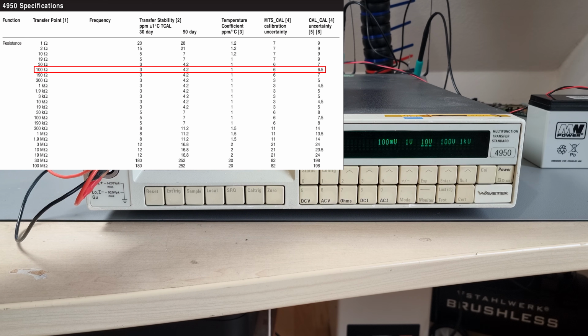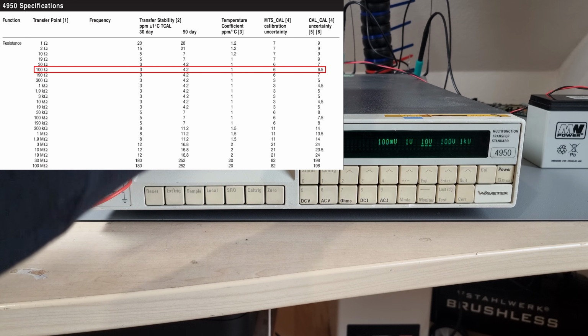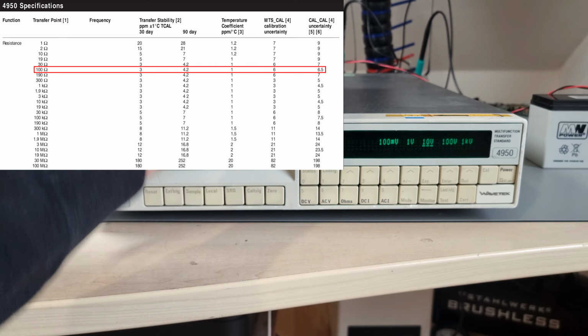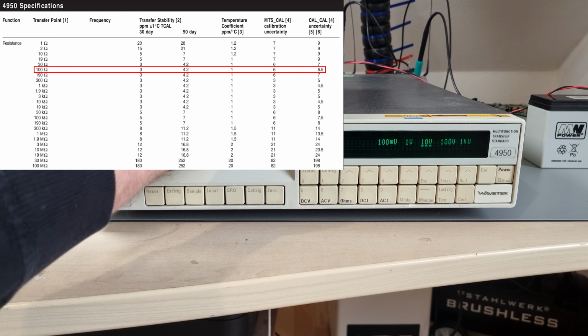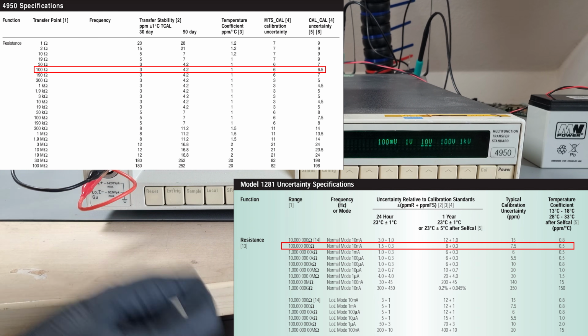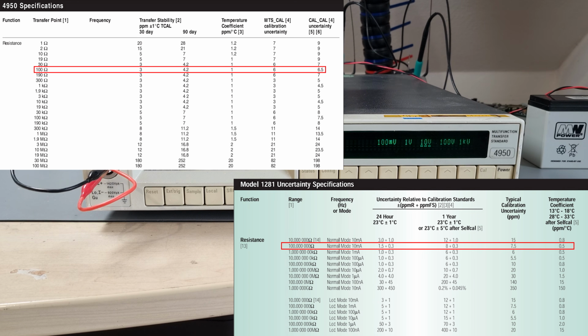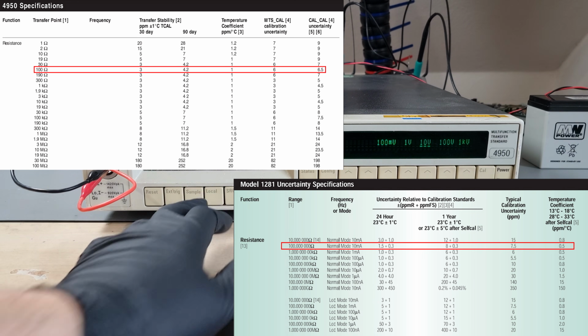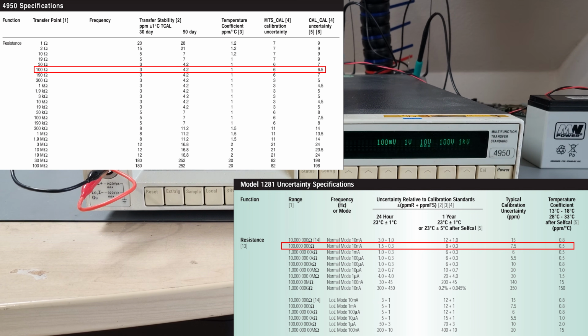Let's say when comparing a 100 ohm standard to another, the 4950 gives you a 30-day 3 ppm uncertainty and a 90-day 4.2 ppm uncertainty, whereas with a multimeter, a day after calibration, you'd instantly fall into the 1-year 8 ppm window. Arguably, the multimeter is not going to sit there 23 hours and 59 minutes after its calibration, impatiently looking at its wristwatch, waiting to lose accuracy all of a sudden. If lucky, a DMM can stay within its 24-hour spec for years.